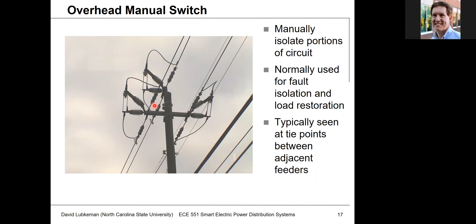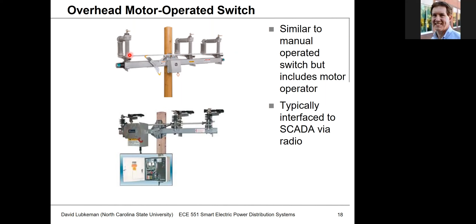And then these can also be motor operated. And the reason you want these motor operated is if you want to automate the restoration process. And so this could be controllable through a SCADA system where you have a motor control, it has communications on it, and the operator could actually talk to the switch and operate it remotely. Usually these types of switches can break load current, but they wouldn't be set up to break a fault current. You need a breaker for that. And so these don't have the same ratings as a recloser or a circuit breaker.